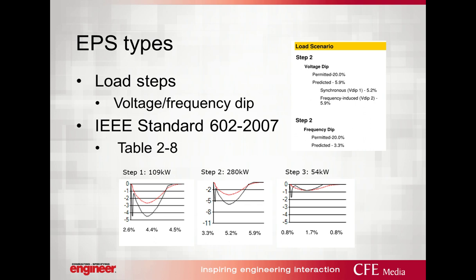Now, managing the size of a generator is done through the use of load steps. This is done with transfer switches and managing the load on each transfer switch. Designers will determine the order that each transfer switch is applied to the system as they come online. Software is used to calculate the resulting voltage dip and frequency dip associated with each load step, and that's what you can see here in these images. You can see step 1, step 2, step 3, and the amount of load on each of them. Now, you can sometimes reduce your generator size by increasing your number of transfer switches and thus reducing the step load that's going to be seen. You're going to coordinate that with approved generator vendors and the software to make those calculations.